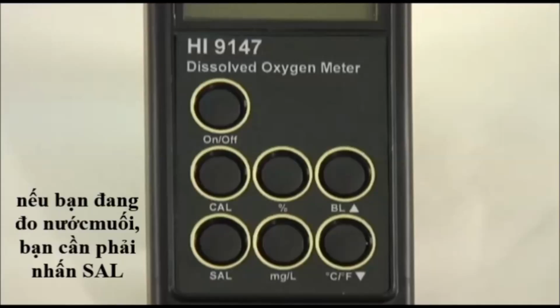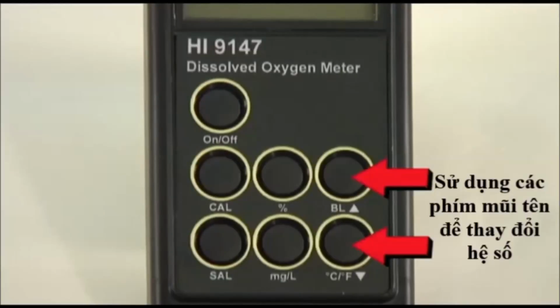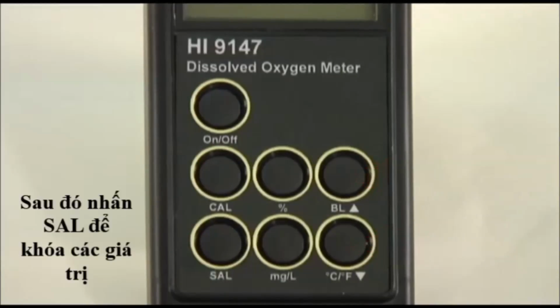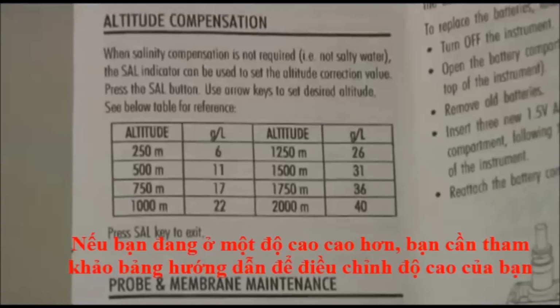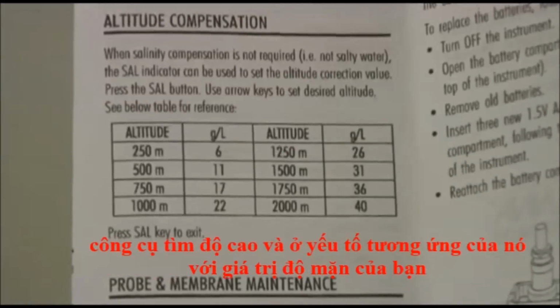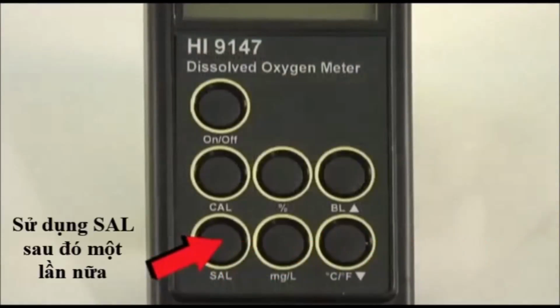Now, if you are measuring salt water, you will need to press Sal to set your salinity value. Use the arrow keys to modify the coefficient, then press Sal to lock in the value. If you are at a higher altitude, you'll need to consult the table in your manual for your altitude correction factor. Find your altitude and add its corresponding factor to your salinity value using the Sal button again.